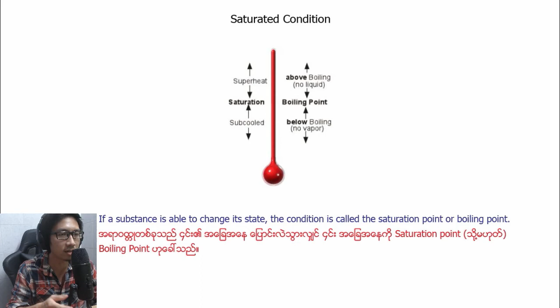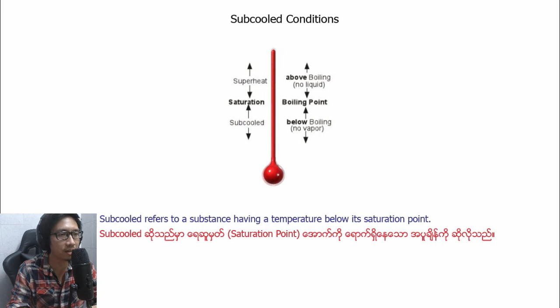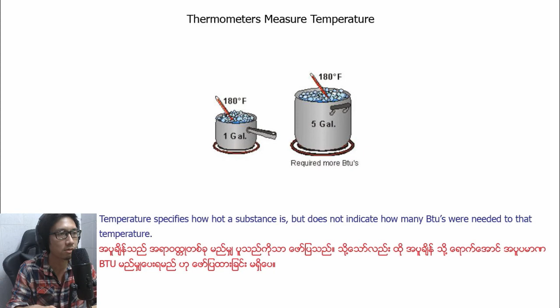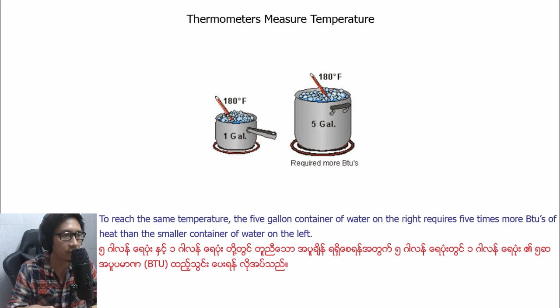Superheat describes a gas that has been heated to a temperature above its saturation point. Subcooled refers to a substance having a temperature below its saturation point. Temperature does not reveal the quantity of heat in a substance. It merely indicates the heat intensity, or how hot a substance is. Temperature specifies how hot a substance is, but does not indicate how many BTU were needed to reach that temperature. To reach the same temperature, the 5 gallon container of water on the right requires 5 times more BTU of heat than the smaller container of water on the left.